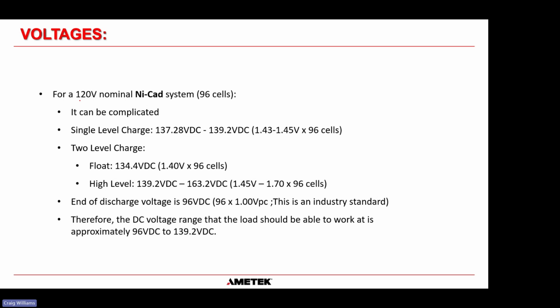Now for NiCad cells, for a 120 volt nominal system, it can be complicated because NiCad manufacturers used to always stipulate this 2-level charge system, where you would float volt the system at 134.4, and then you would have a high level charge or a boost charge at 139.2 up to 163.2 volts. And they would say that you would have to do this high level charge on a regular basis, maybe quarterly or semi-annually.